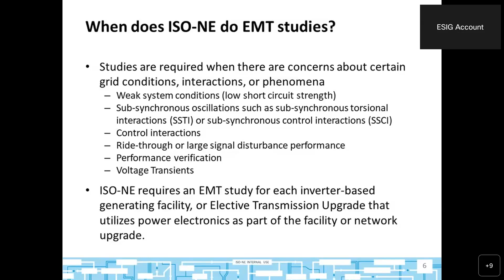At the ISO, we use Manitoba HVDC's PSCAD software. It's been around for a long time and has a lot of features we like. We've been requiring studies in it since around 2014. We perform EMT studies as part of the system impact study for all interconnection requests for inverter-based resources. The study normally includes both N-1 and N-1-1 testing to identify low system strength concerns or other ride-through issues.